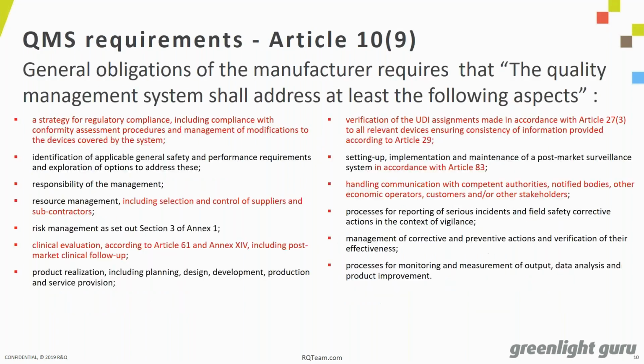So the first thing we want to touch on is the quality management system, the base for a lot of your devices. While compliance with ISO 13485:2016 addresses a lot of the new requirements under the MDR, there's still some additional key requirements which have to be addressed by the QMS that you should be aware of. So manufacturers are going to have to document a strategy for regulatory compliance, including compliance with conformity assessment procedures. Outside of, again, 13485, manufacturers have to verify UDI assignments for devices, both initially as the devices are launched and then periodically after the device is released.